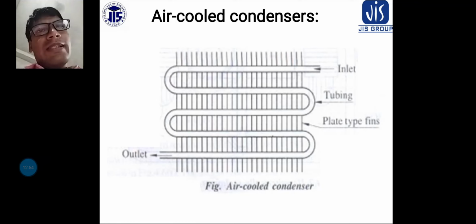If I am talking about the remote air cooled condenser, then these condensers may be horizontal or vertical. They can be located either outside or inside the building, and usually use propeller fans because they have low resistance to airflow and free air discharge. They are used on systems above 10 tons and are available up to 125 tons. Systems above 125 tons usually have two or more condensers.